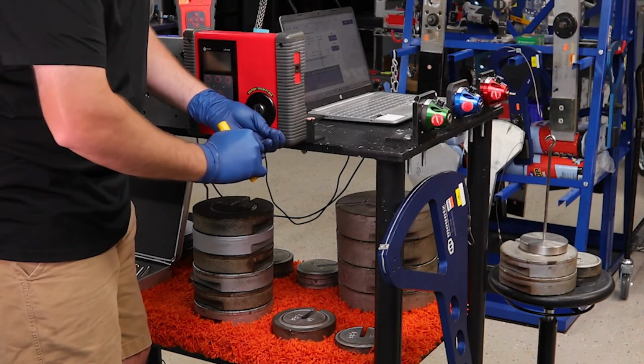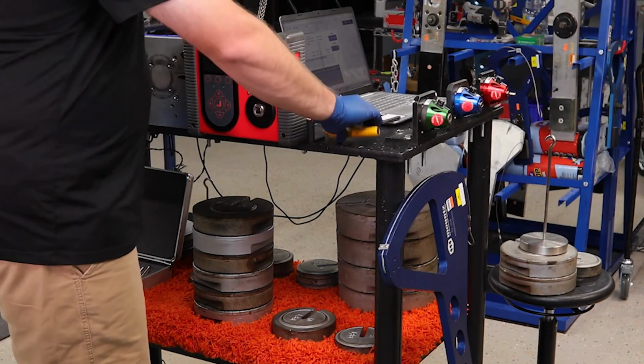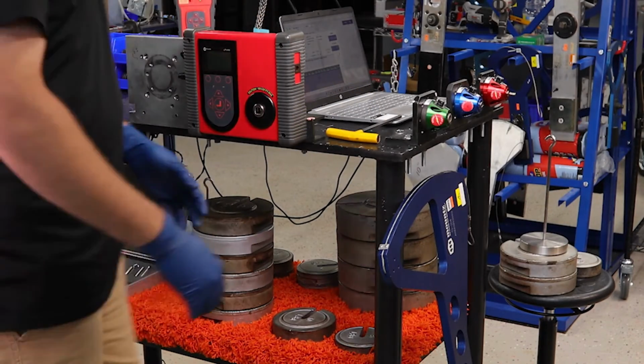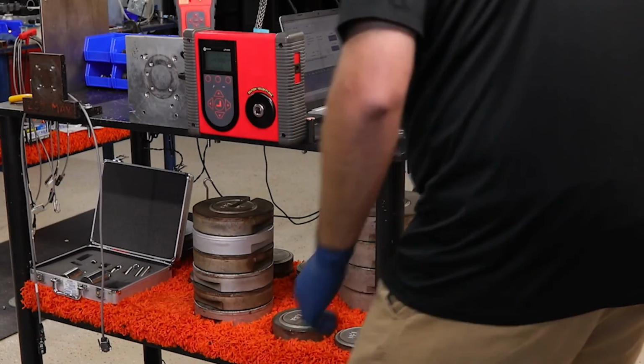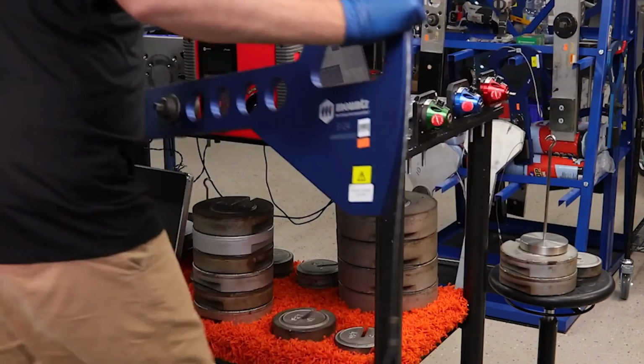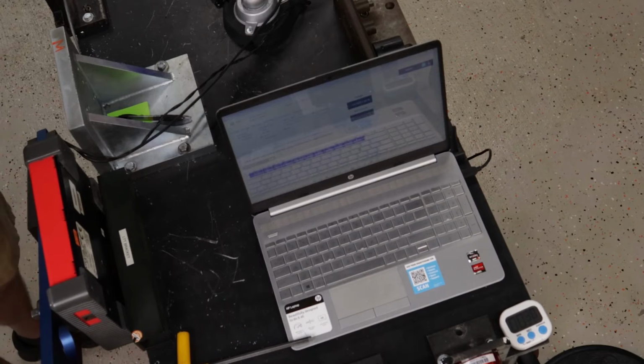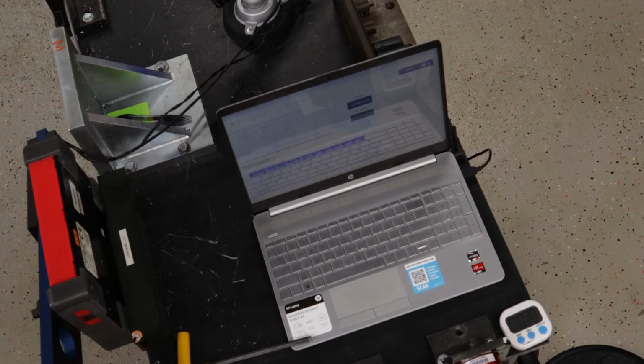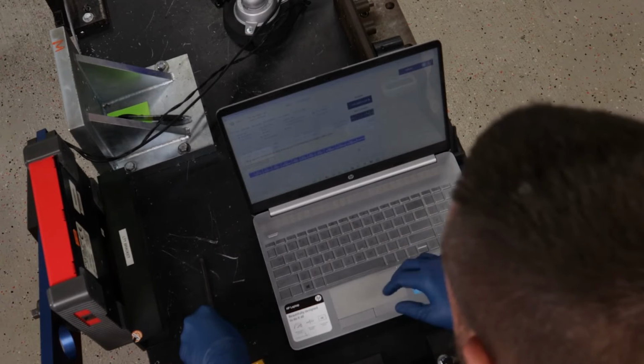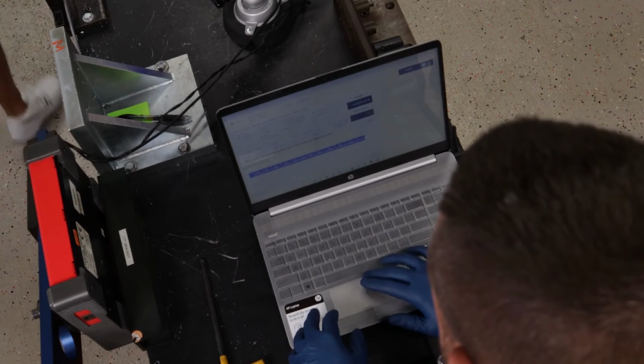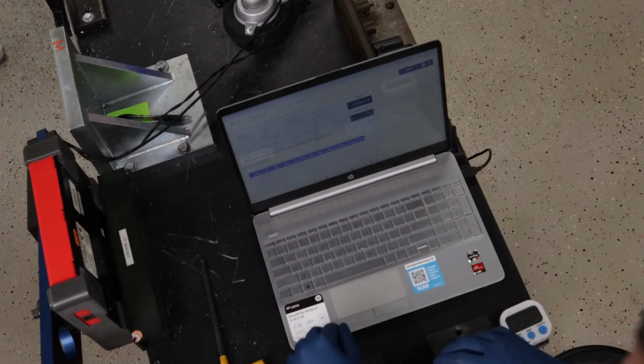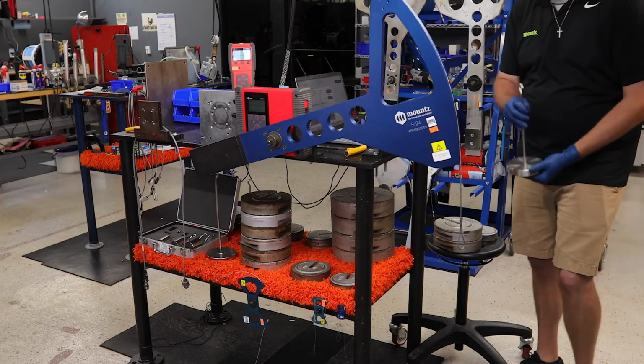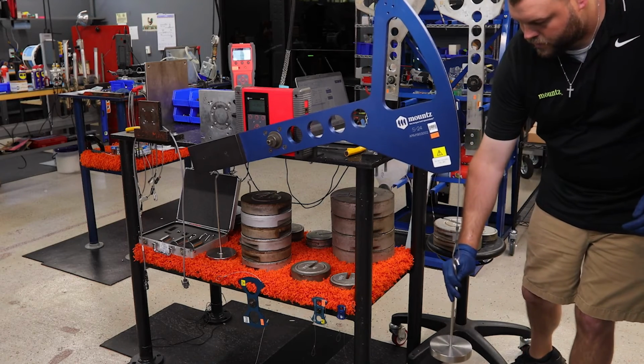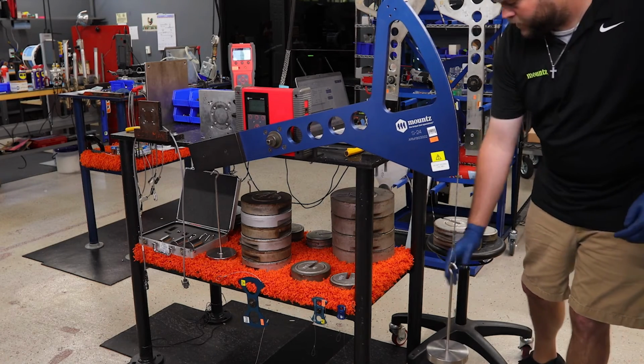We want to first make sure that we have our sensor mounted to the correct bracket. In this case, we are calibrating our LTT 100F, so it has a built-in 100 foot-pound transducer. Just like I mentioned when we were talking about the weights and hangers, we are using a 2-foot segment arm here with a total of 50 pounds of weights.